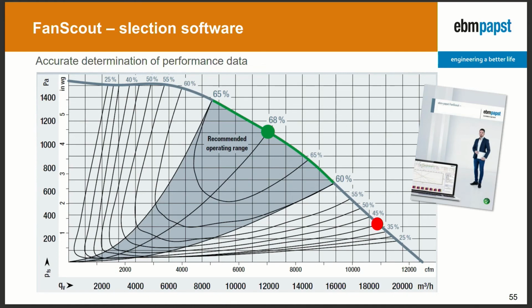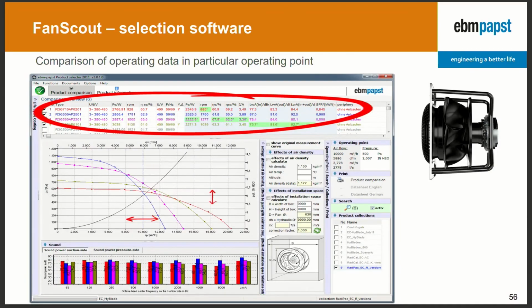Our fan can also, by using a certain intelligence, just measure the airflow with a pressure tap, which I explained before, and the speed. Together we can determine where the fan is operating, so in which duty point. Is it a duty point which is, let's say, outside of the recommended area, at a poor efficiency level? This is something you need when you want to monitor the performance of the unit, and this can be done by using this information in addition with the sensor. The data get compared in our selection software, so you can be sure that you find the right product with the highest efficiency or the lowest noise.